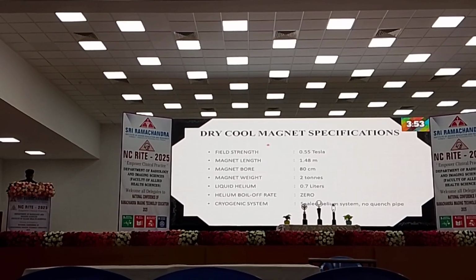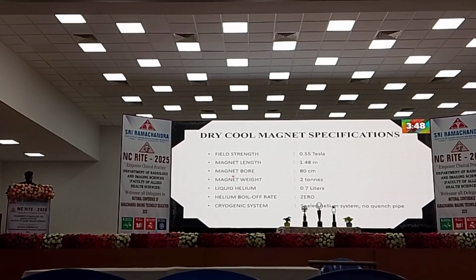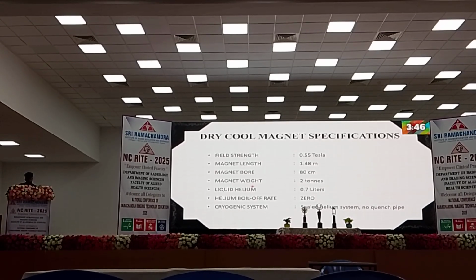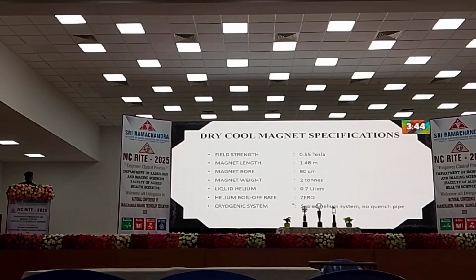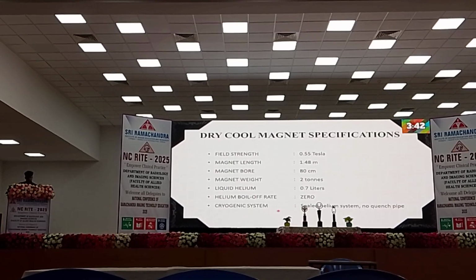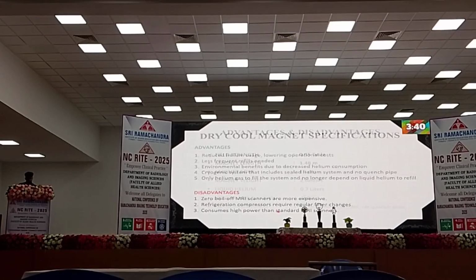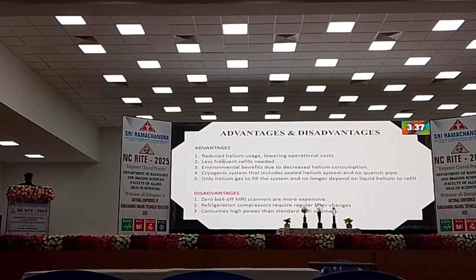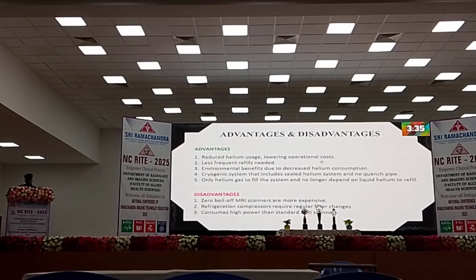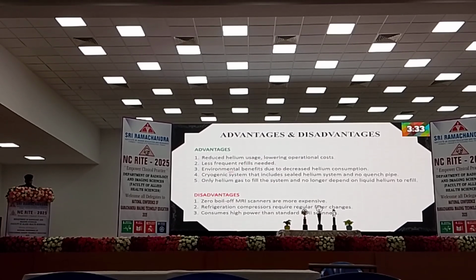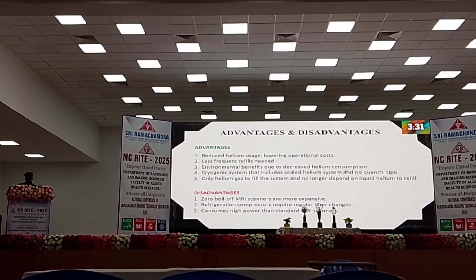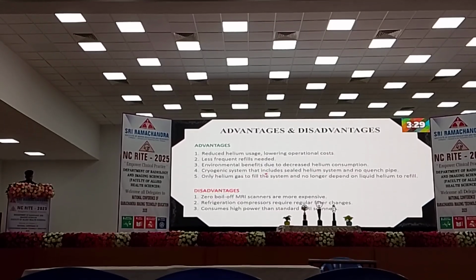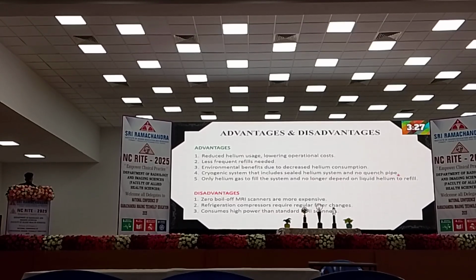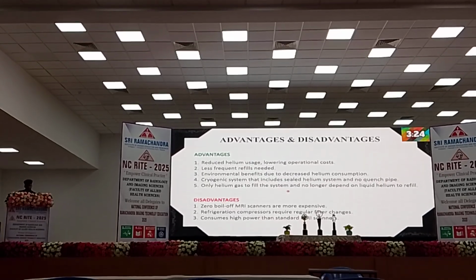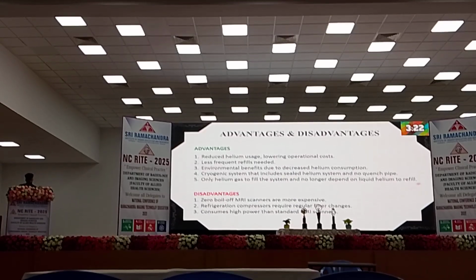The specifications of the dry-cooled magnet are 0.55 Tesla field strength, 80 cm magnet bore, 2 tons magnet weight, 0.7 liters of liquid helium, zero helium boil-off, and a sealed cryogenic system that doesn't require a quench pipe. Advantages and disadvantages. Advantages are reduced helium usage, lowering operational cost, less frequent refills needed, environmental benefits due to decreased helium consumption, and a cryogenic system that includes a sealed helium system and no quench pipe. Only helium gas is needed to fill the system, which no longer depends on liquid helium to refill.